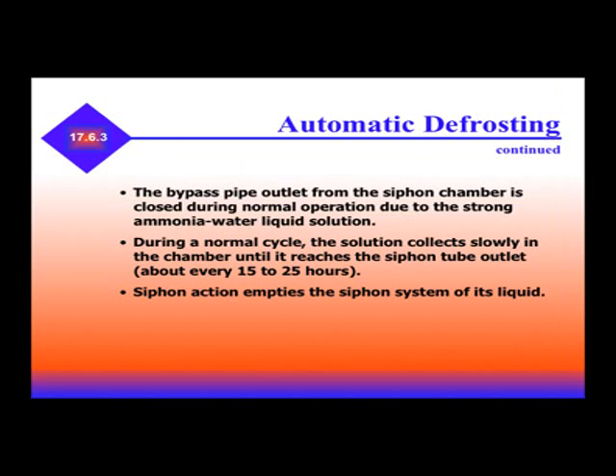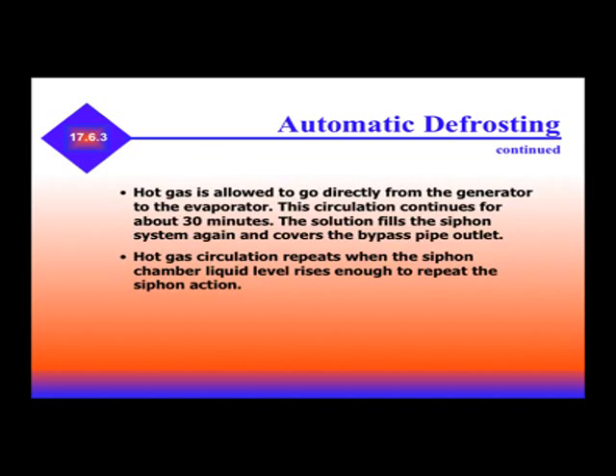The bypass outlet in automatic defrost from the siphon chamber is closed during normal operation due to the strong ammonia-water liquid solution. During normal cycle, the solution collects slowly in the chamber until it reaches the siphon tube outlet. The siphon action empties the siphon system of its liquid. Hot gas is then allowed to go directly from the generator to the evaporator for about 30 minutes. The solution fills the siphon system again and covers the bypass pipe outlet. Hot gas circulation repeats when the siphon chamber liquid level rises enough to repeat the siphon action. In other words, no electromagnetic valves are needed — it's all based on the level of the solution in the siphon chamber.